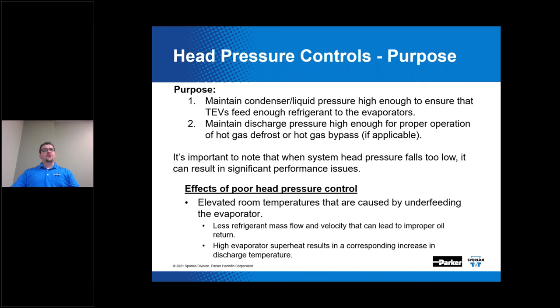The purpose of head pressure control involves two main things: one, it maintains your condenser or liquid pressure high enough to ensure that the TEVs can feed enough refrigerant to the evaporators; and two, it maintains your discharge pressure high enough for the proper operation of your hot gas defrost or hot gas bypass, if the systems have those features.